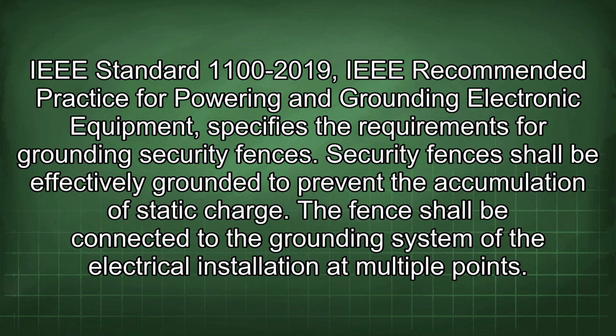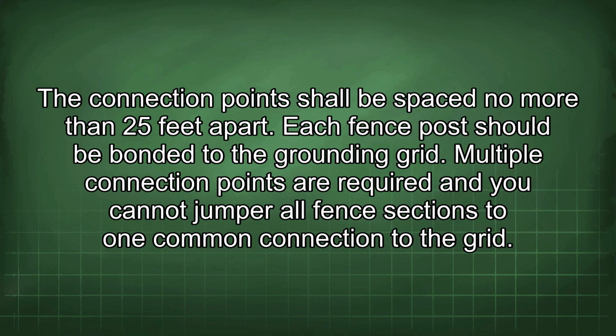Security fences shall be effectively grounded to prevent the accumulation of static charge. The fence shall be connected to the grounding system of the electrical installation at multiple points. The connection points shall be spaced no more than 25 feet apart. Each fence post should be bonded to the grounding grid. Multiple connection points are required, and you cannot jumper all fence sections to one common connection to the grid.